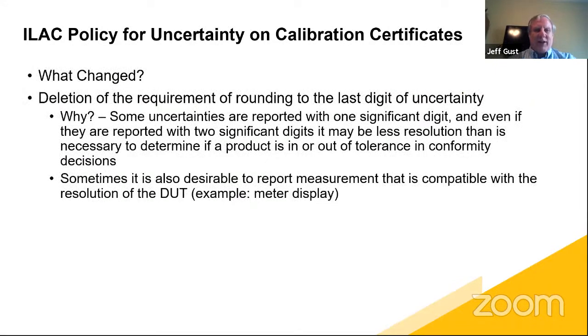So the part that really changed was the deletion of the requirement of rounding to the last digit of uncertainty. And the reason why is because some uncertainties are reported to one significant digit. And even if they are reported to two significant digits, it may be less resolution than is necessary to determine if a product is in or out of tolerance with a conformity decision. So maybe you're trying to determine, is my unit in or out of tolerance? And your uncertainty is 190 microvolts, but you've got 1 microvolt resolution on the device under test. If that makes a difference to whether determining if your unit is good or bad, you need that digit.